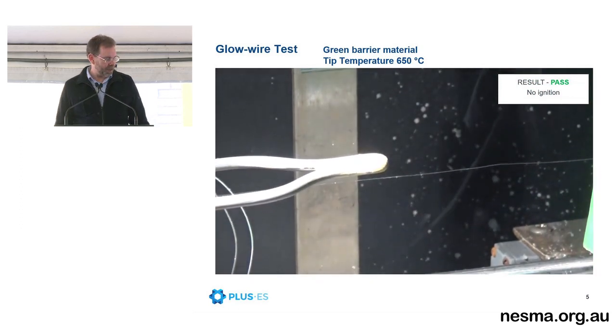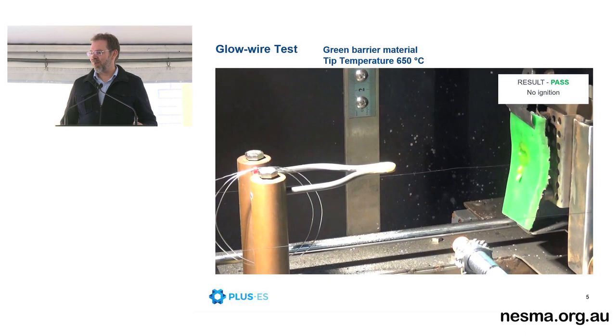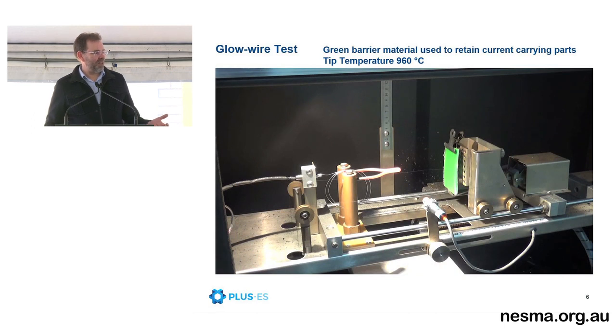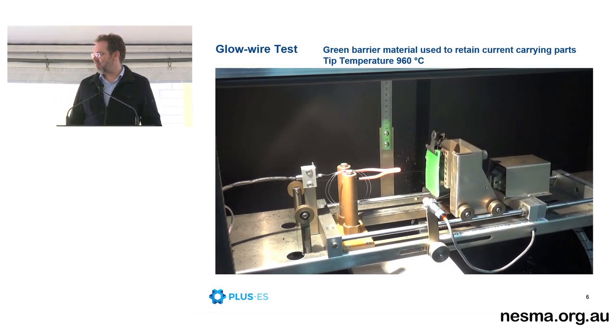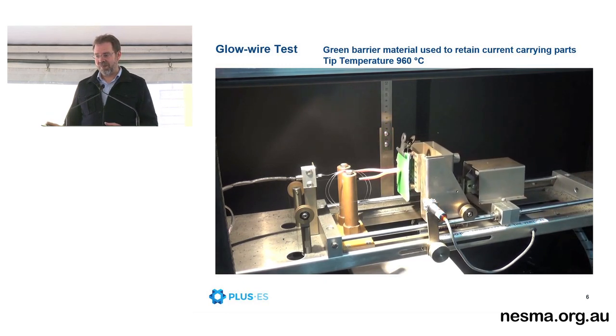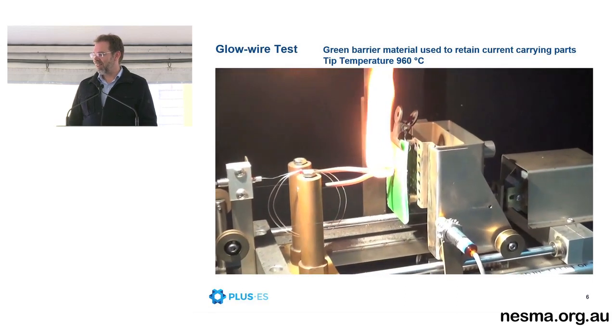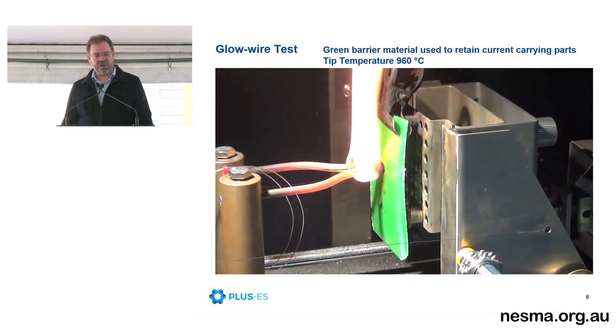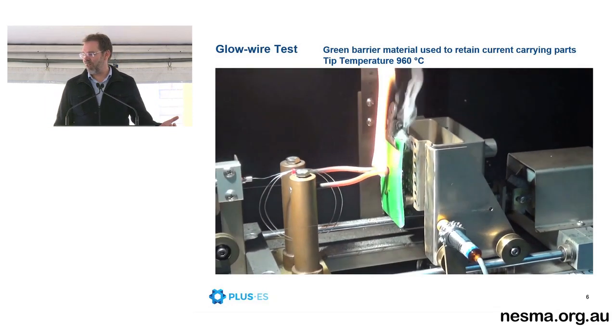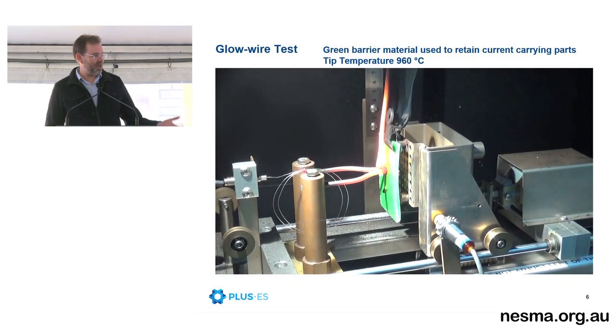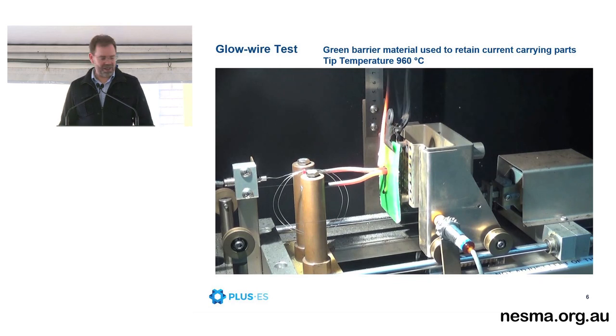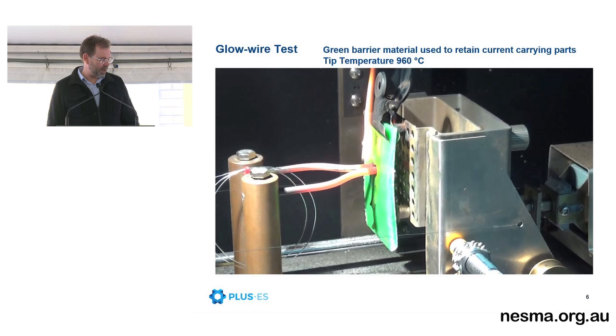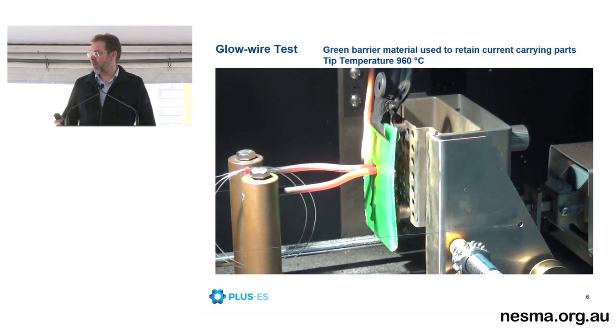It's these criteria. So it's interesting because, okay, Max explained, we discovered a support that was a well-used product, and it failed the glow wire. Glow wire's not in AS3439. AS3439 has short circuit tests, and these supports were excellent. They passed the short circuit test, and now we're starting to test to the new standard, and we know it doesn't meet the glow wire requirements. So how can we certify a product? How can we issue a certificate on a product where we know the supports, even though they might pass the short circuit test, fail the glow wire? So yeah, it did bring up a sticky situation. Incidentally, in the end, we didn't end up issuing that certificate based on the glow wire knowledge.